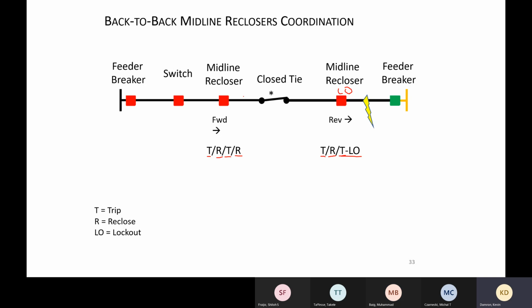Oh, so you're saying here? Are we talking about a fault right there? No, further next to the feeder breaker on the left. Like next to the switch on the left. Let me erase this, and so you're talking of the feeder breaker here? Yes. Between the feeder and the switch? Yes. Oh, in that case, if we were to have a fault there, then I only have a source from one end, right? This feeder breaker's open, so I don't have a source at this end. So if I have this source.